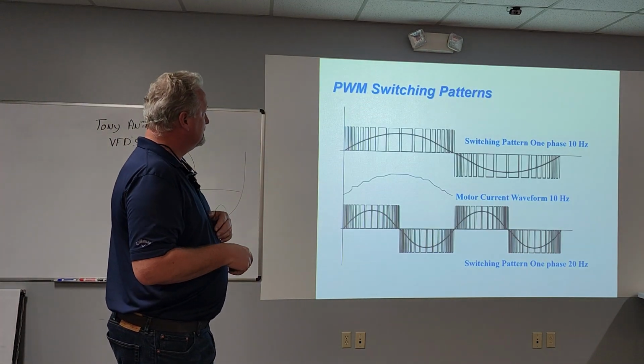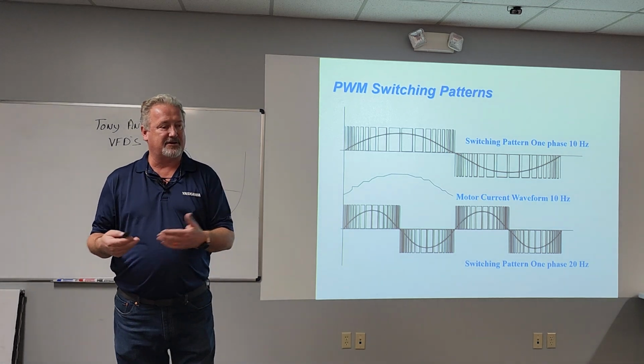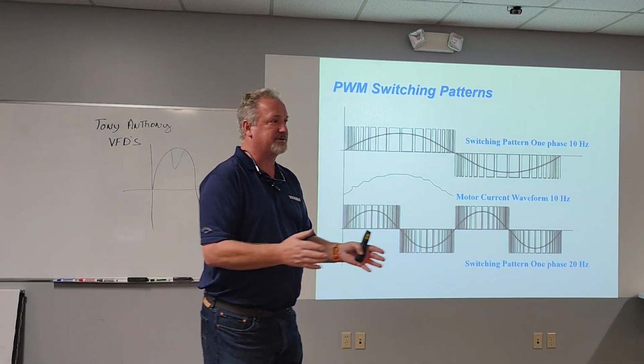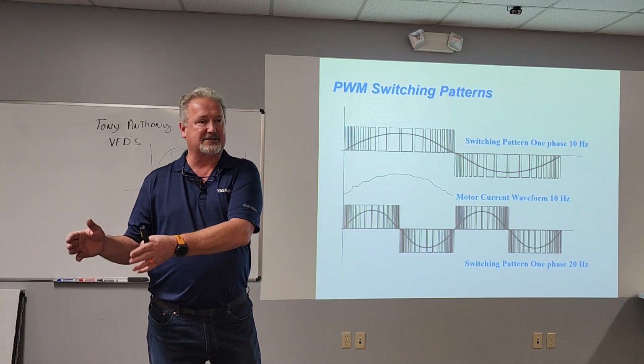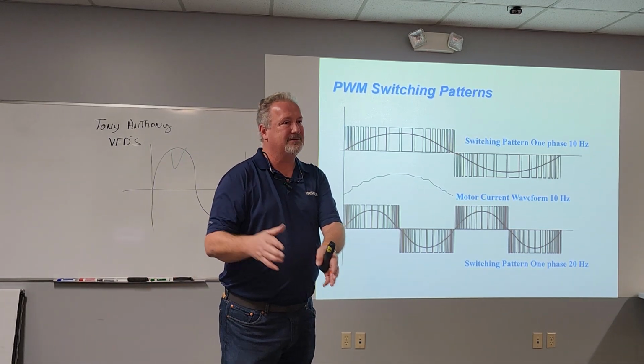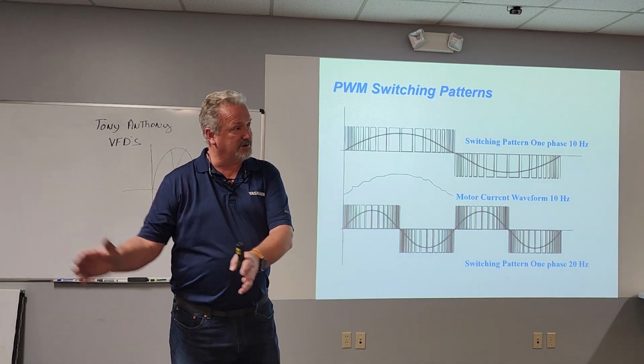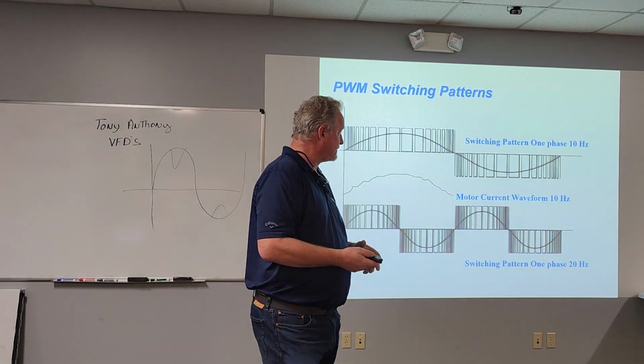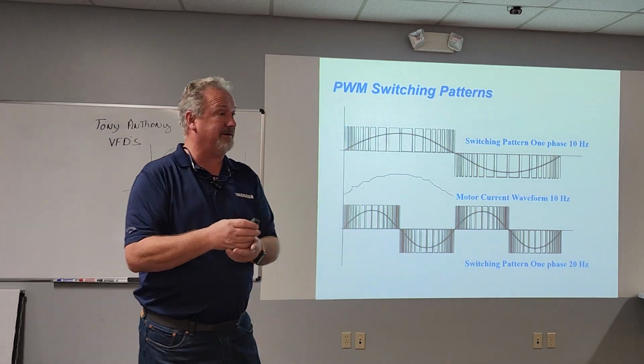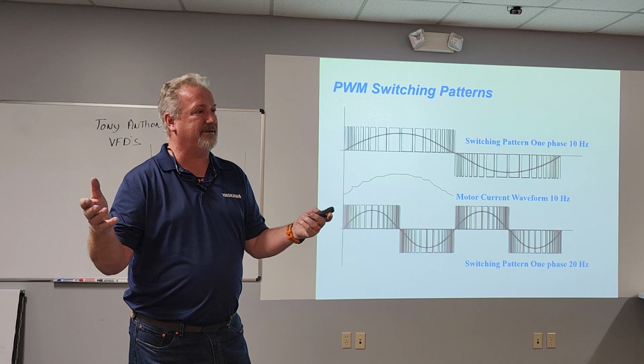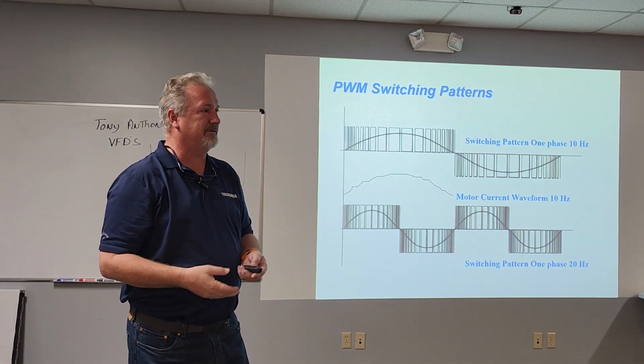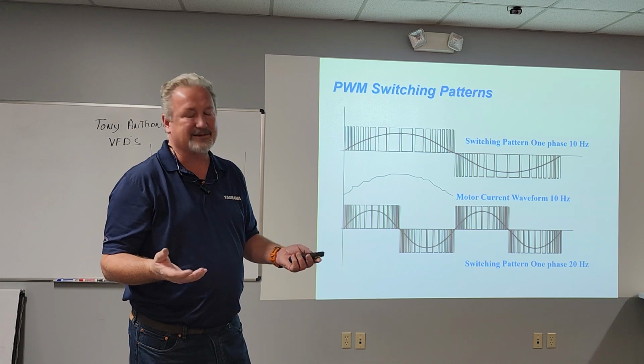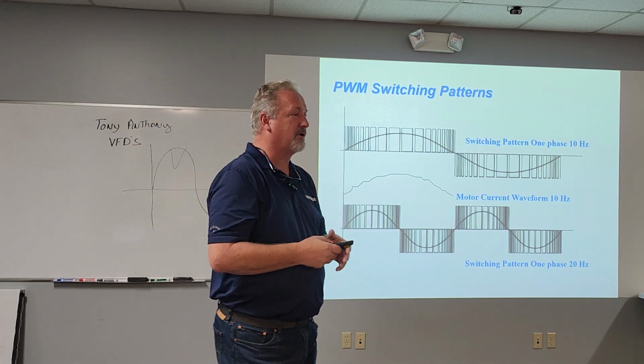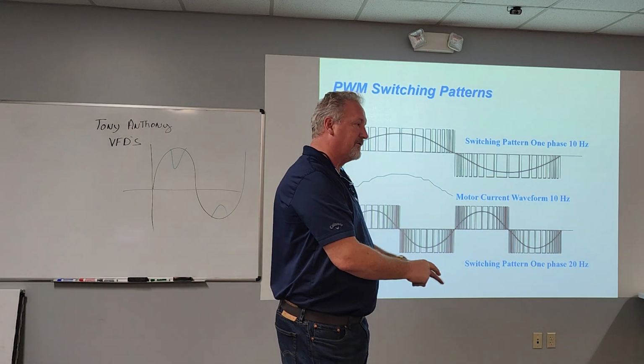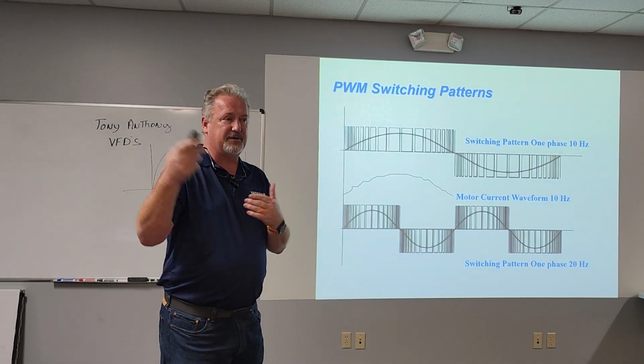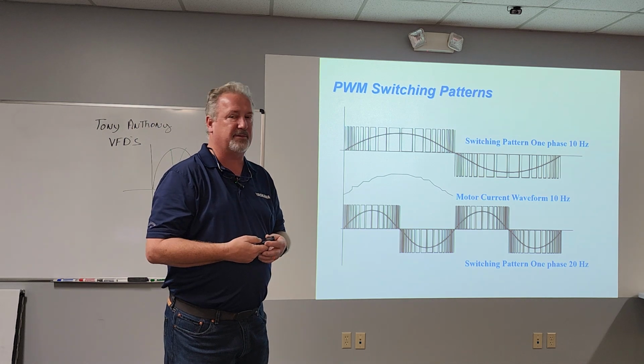And you can see here what a drive does, obviously, and I guess I should have mentioned this in the beginning. Obviously, the way a drive works is we change the frequency, right? So if we've got a motor running in the Americas at 60 hertz, we can slow it down to 30 hertz, saves energy. We'll talk about that here in a little bit. We also lower the voltage down. We control voltage and frequency at the same time. So if you're checking a drive, and this happens, and we still get the calls all the time. Somebody walks up to a drive and they go, hey, drive's running 30 hertz, and I checked the output voltage, it's only 230. That's right. Our volts per hertz curve, as we're changing frequency, we're changing voltage at an equal proportion. And so if you're a 460 drive and you run 30, your output voltage is going to be around 230.